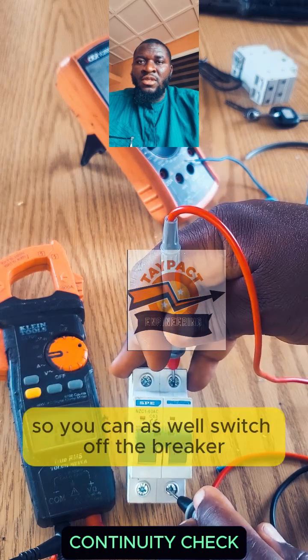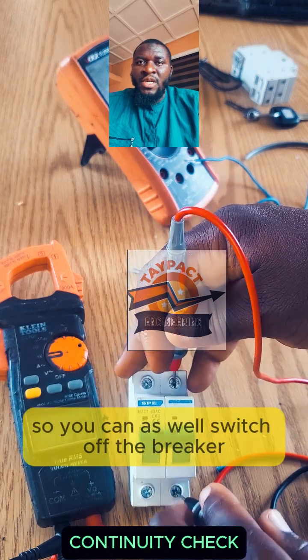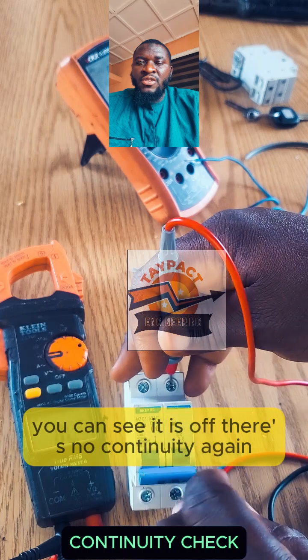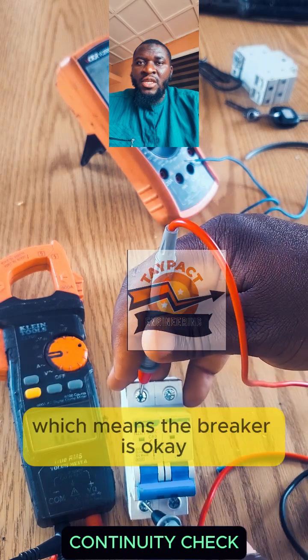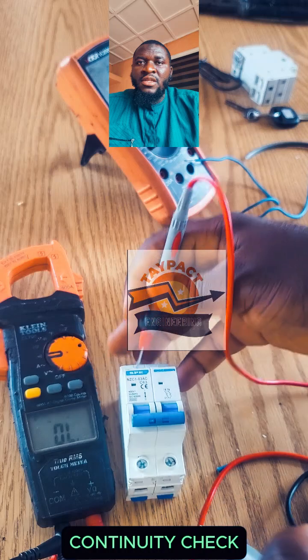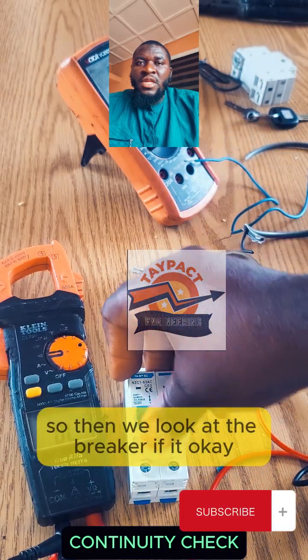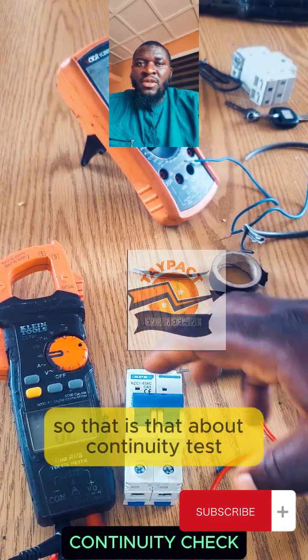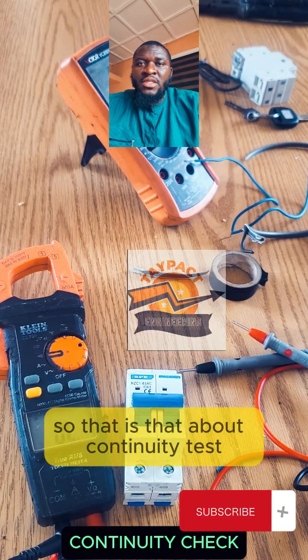So you can as well switch off the breaker. You can see it is off. There's no continuity again, which means the breaker is okay. Then we can switch it on back. So then we know that this breaker is okay. So that is it about continuity tests.